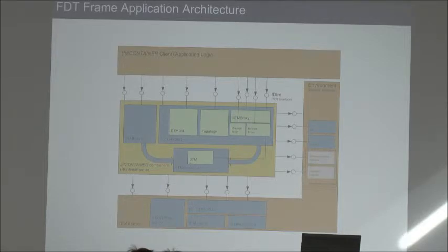The DTM catalog gives you access of the DTM catalog, of course, which DTMs, which device types are installed. The registration information, the registry was one question in one of the presentations before. This is scanned by the catalog, or when building up the catalog, and also the manifest files are scanned to see what's installed on the machine.